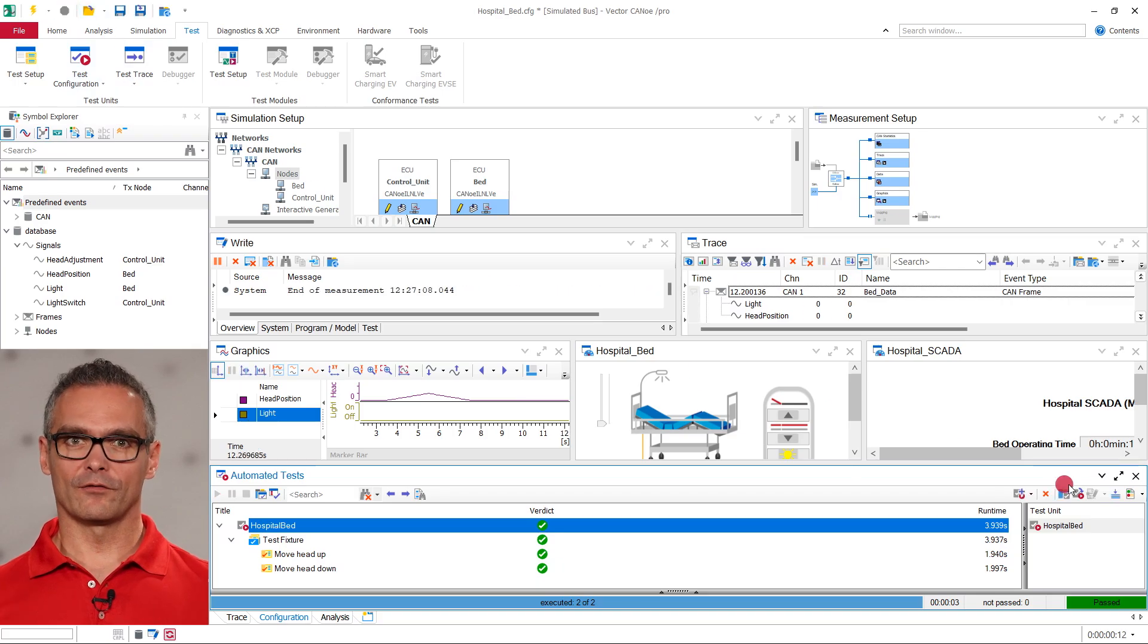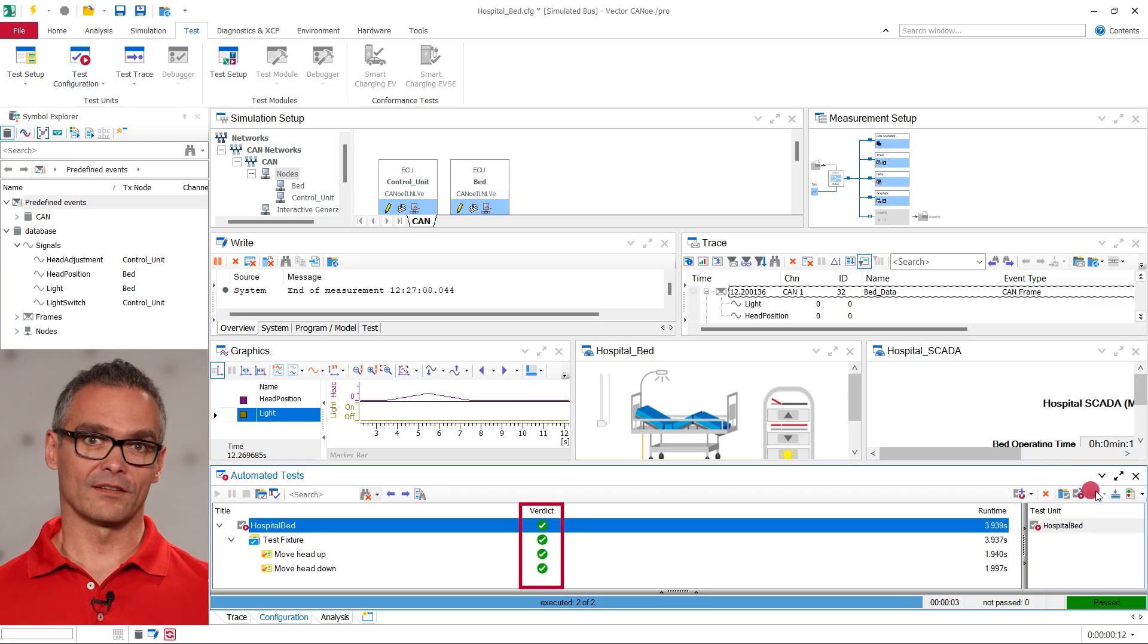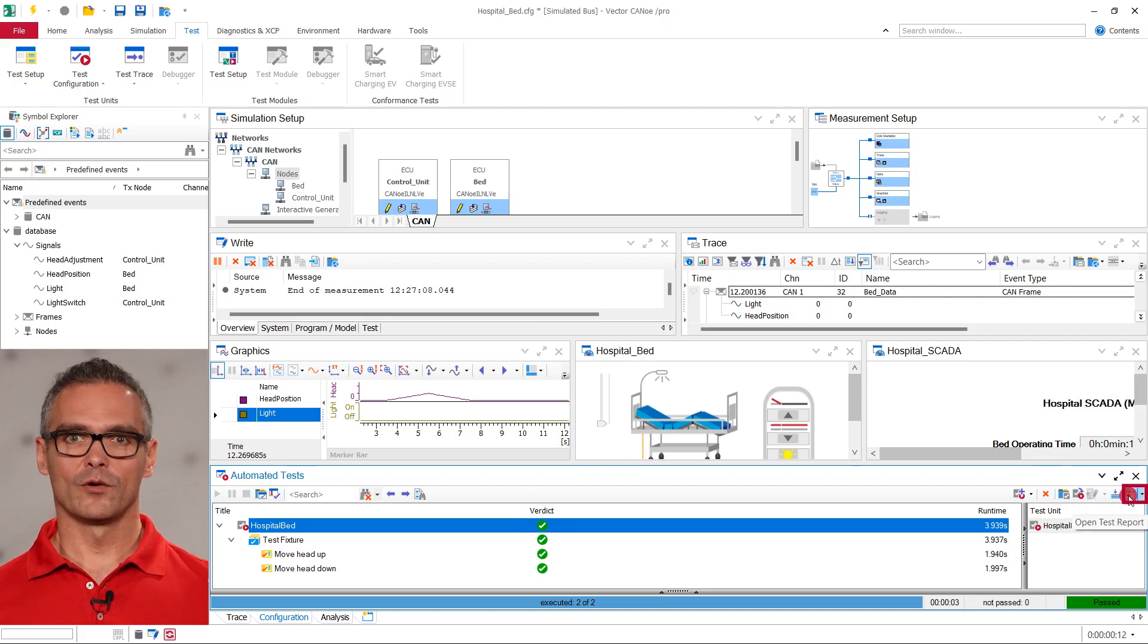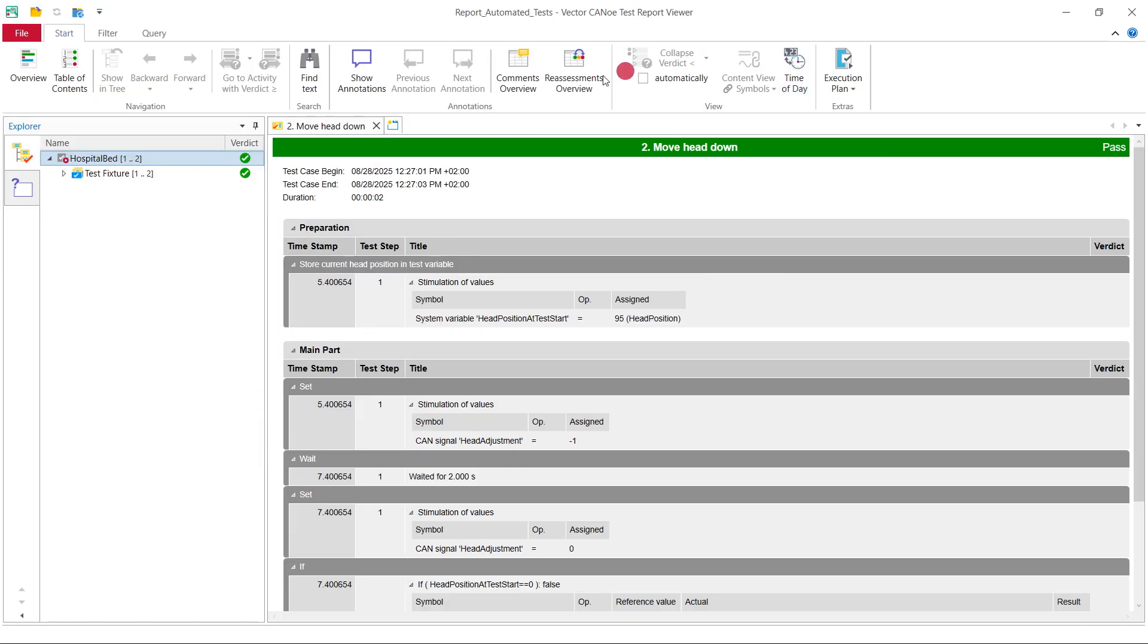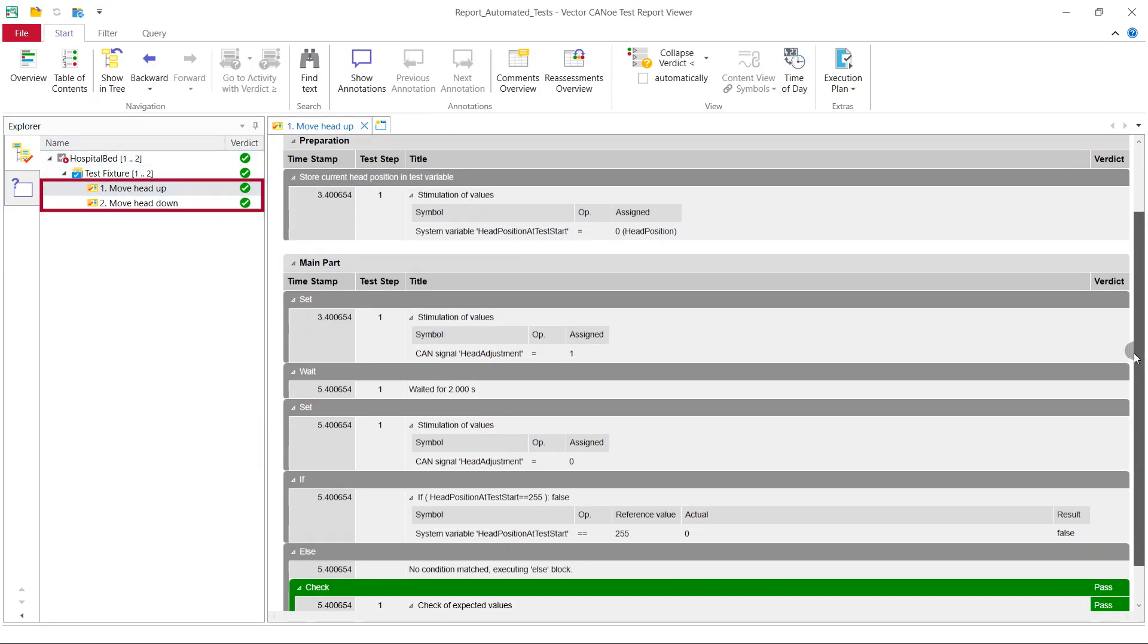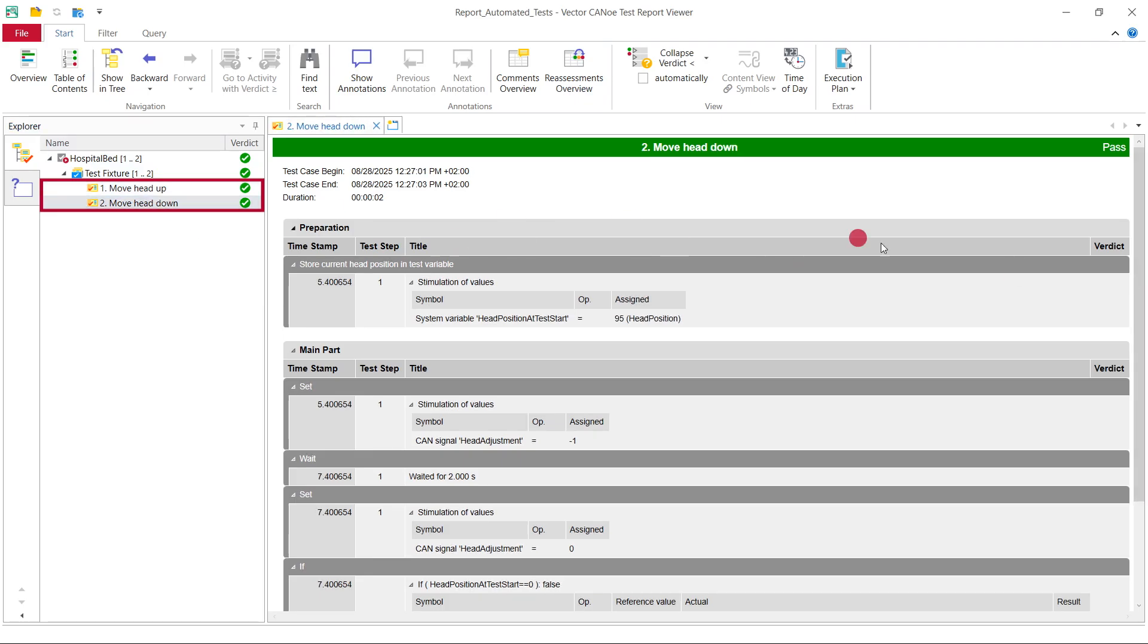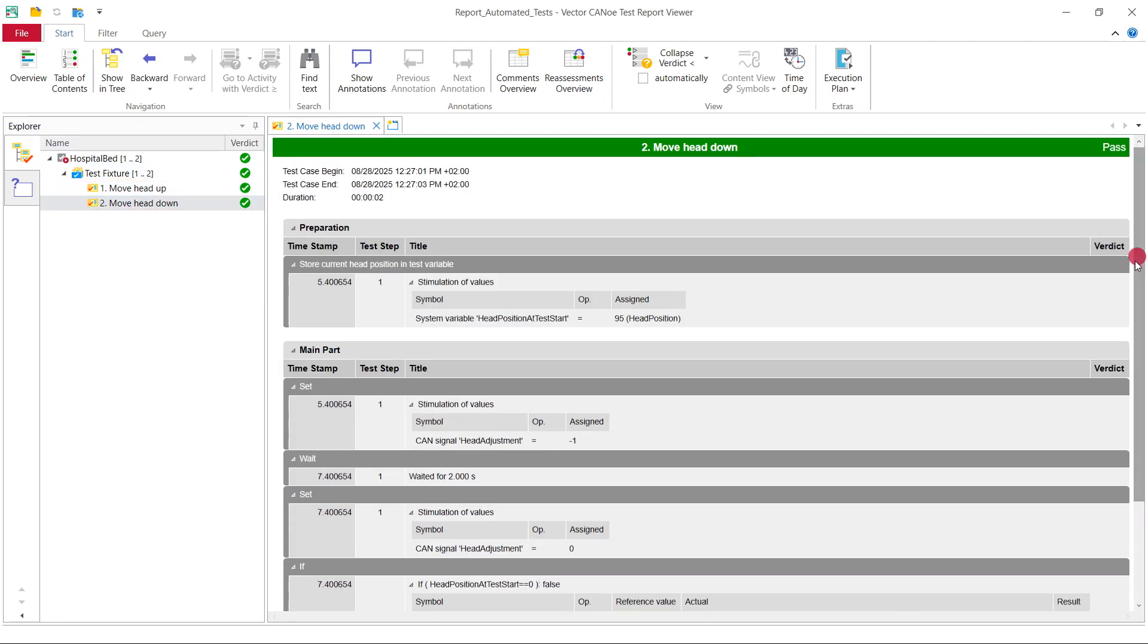When the tests are finished, we can see the verdict for each test case. As expected, both tests pass. To get more details, we can open the automatically created test report and see each test step as a row. This report can be attached to the relevant documentation to speed up the verification and validation process of new devices.